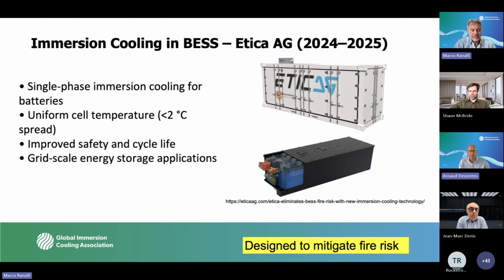Here you have an example with the company Etica AG, who is a partner of Shell, that provides BESS cooled with immersion cooling with unrivaled safety. The risk is really contained at the module level, so that if any thermal runaway happens, because you cannot forbid any cell thermal runaway, you are sure that you have no contamination from one module to the other, from one battery pack to the other, and therefore the entire container does not burn, which is unique, because with other technologies, when there is a thermal runaway, generally for the BESS, the complete container burns.